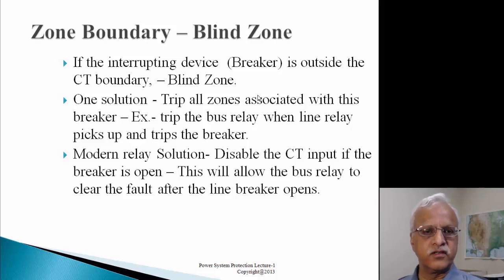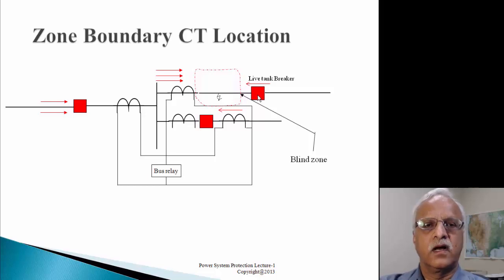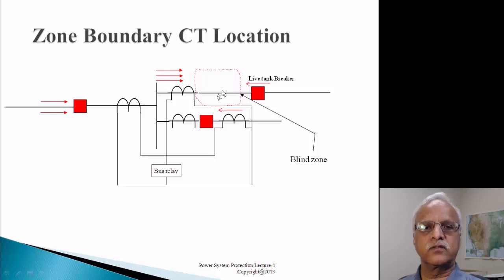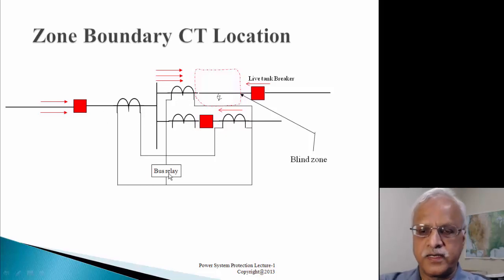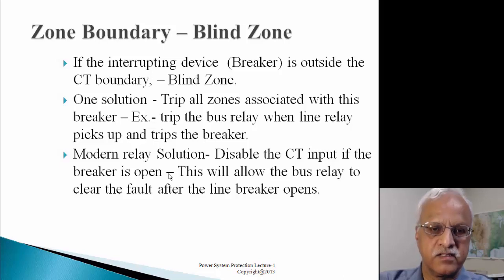The solution in modern relays is: as soon as the live tank breaker opens, they remove the current accounted for in the bus relay. If this current becomes zero but the sum of the remaining currents is not equal to zero, the bus relay also operates. This is one of the methods used to address blind zones.